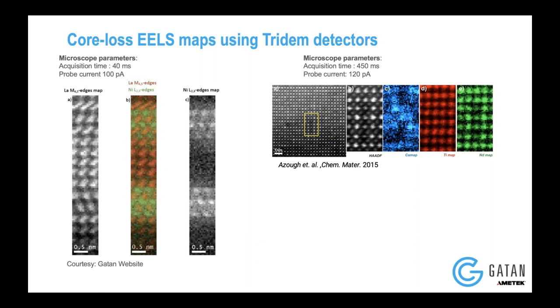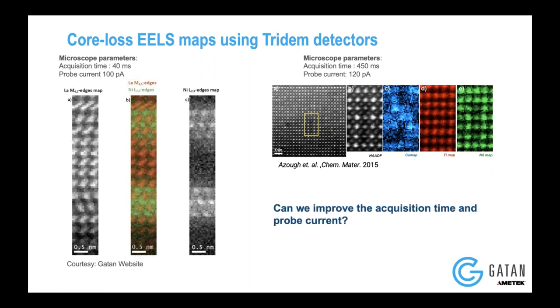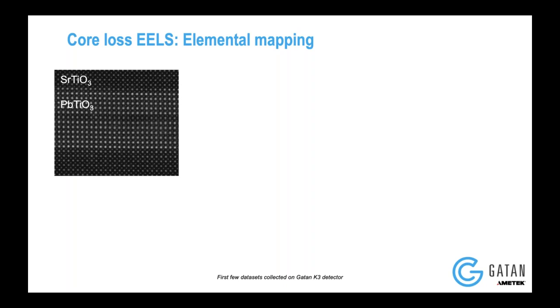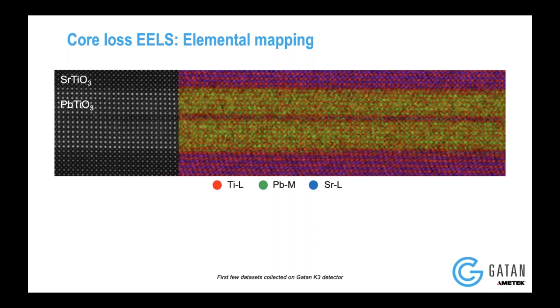The challenge was to improve the acquisition time as well as lower the probe current to make sure that chemical mapping could be done with very little time. When K3 was installed, I was lucky enough to be a postdoc at exactly that time at LBL. We have this very nice example of a strontium titanate / lead titanate superlattice, and it's amazing that with the help of elemental mapping using the K3 — one of the first datasets collected on K3 — you can actually see even a single unit cell of strontium titanate.